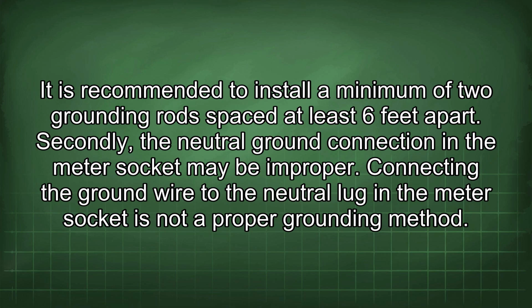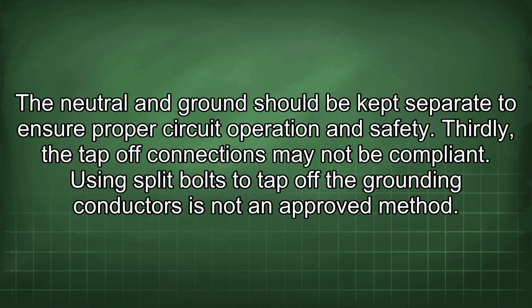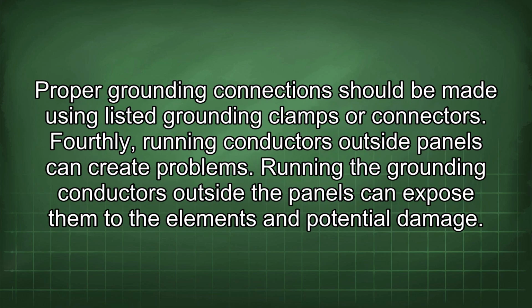Secondly, the neutral ground connection in the meter socket may be improper. Connecting the ground wire to the neutral lug in the meter socket is not a proper grounding method. The neutral and ground should be kept separate to ensure proper circuit operation and safety. Thirdly, the tap-off connections may not be compliant. Using split bolts to tap off the grounding conductors is not an approved method. Proper grounding connections should be made using listed grounding clamps or connectors.